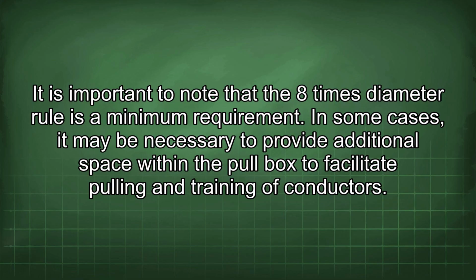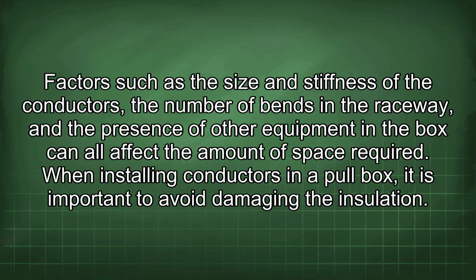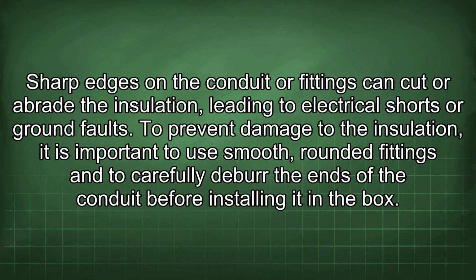In some cases, it may be necessary to provide additional space within the pull box to facilitate pulling and training of conductors. Factors such as the size and stiffness of the conductors, the number of bends in the raceway, and the presence of other equipment in the box can all affect the amount of space required. When installing conductors in a pull box, it is important to avoid damaging the insulation. Sharp edges in a conduit or fittings can cut or abrade the insulation, leading to electrical shorts or ground faults. To prevent damage to the insulation, it is important to use smooth, rounded fittings and to carefully deburr the ends of the conduit before installing it in the box.